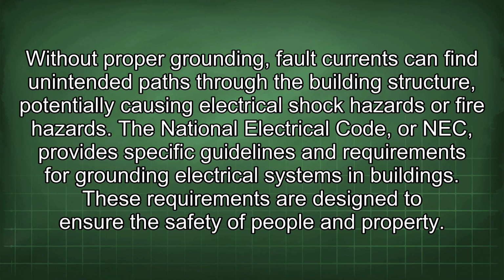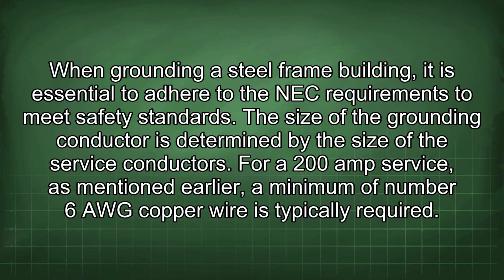The National Electrical Code, or NEC, provides specific guidelines and requirements for grounding electrical systems in buildings. These requirements are designed to ensure the safety of people and property. When grounding a steel frame building, it is essential to adhere to the NEC requirements to meet safety standards. The size of the grounding conductor is determined by the size of the service conductors. For a 200 amp service, as mentioned earlier, a minimum of number 6 AWG copper wire is typically required.